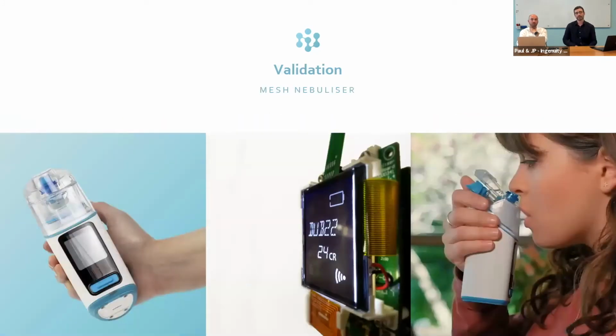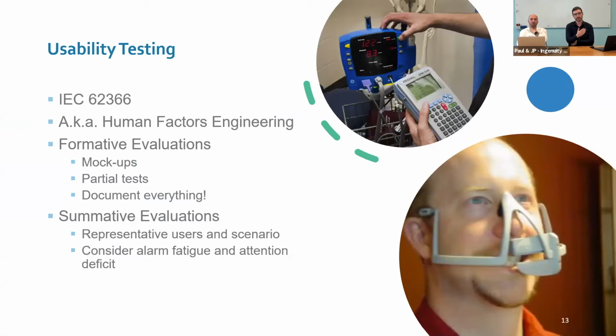Now, validation is where you try to put it into the hands of users or people who represent the users in the actual environment. This is an example of another type of mesh nebulizer, which is handheld and battery powered. So if we go into the next one, you can see how this ties into your usability. So 62366, as I mentioned, is also known as human factors engineering in the States. You want to do formative evaluations as an early mock-up and document everything you can. People miss that opportunity often. And then the validation occurs at the end where you do summative evaluations with representative users in a representative scenario. You want to consider things like alarm fatigue and attention deficit as well.